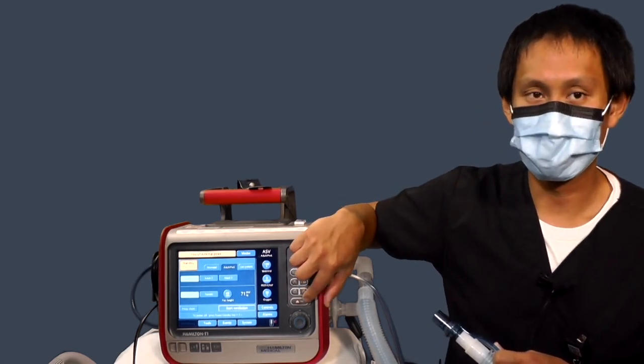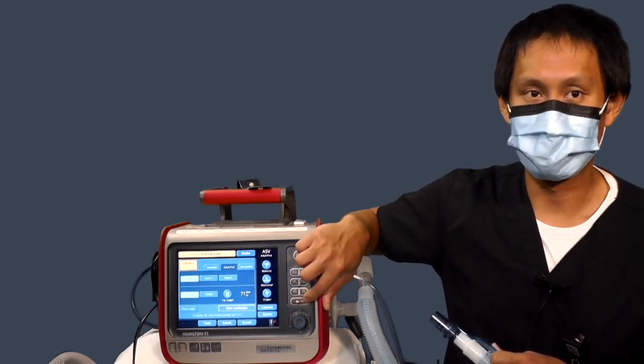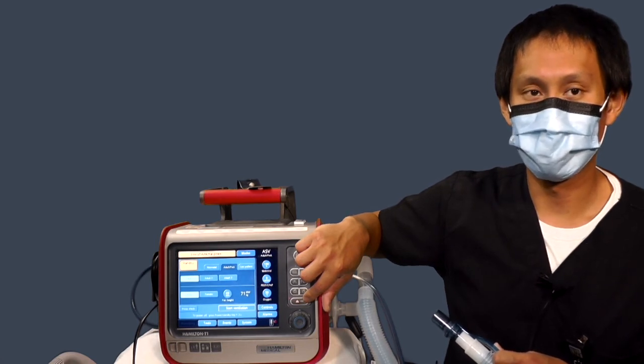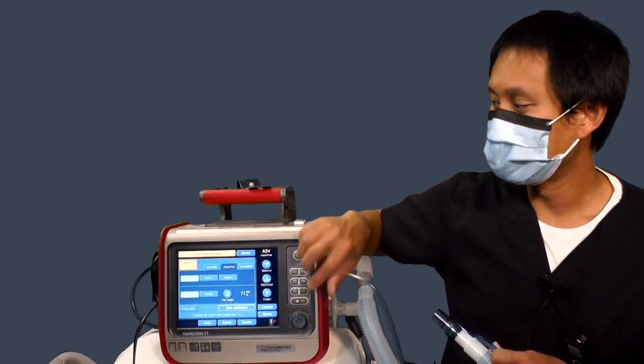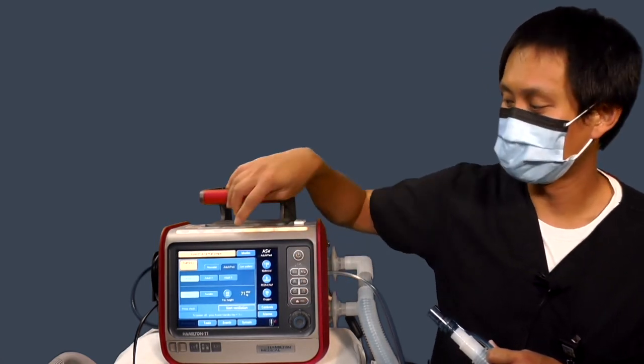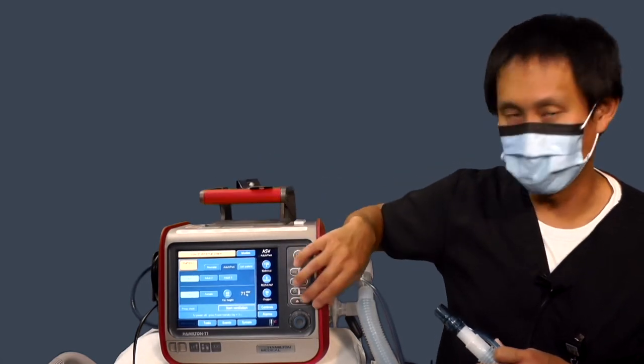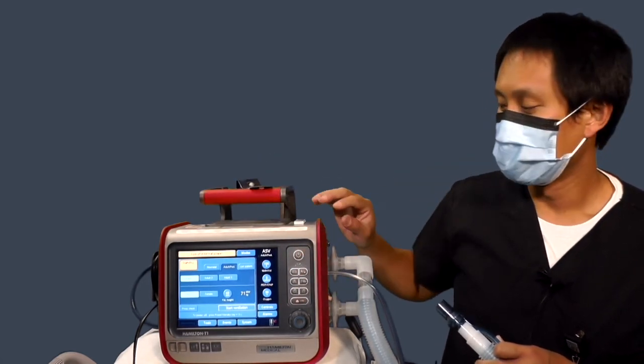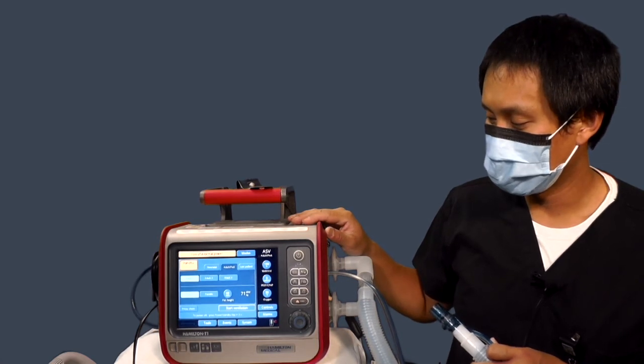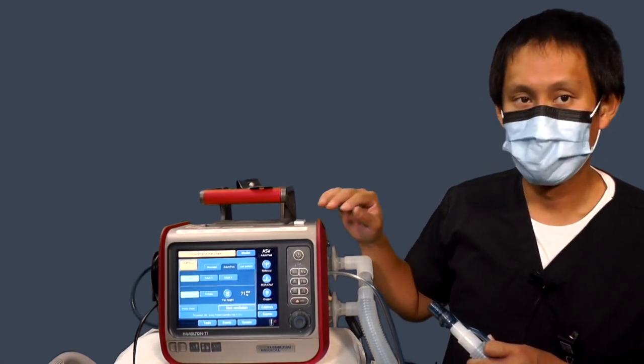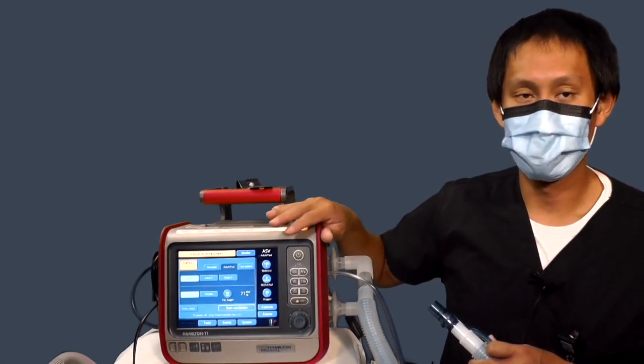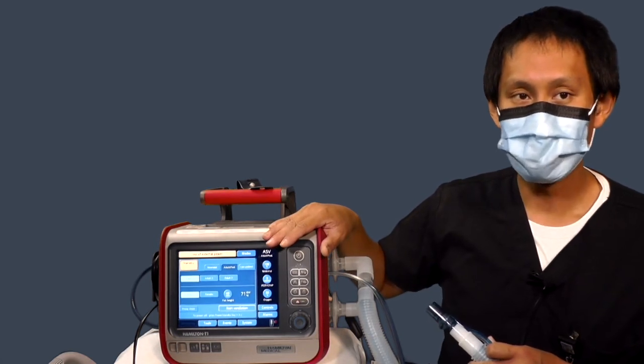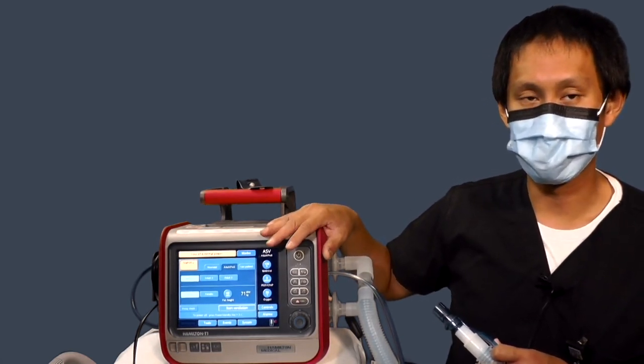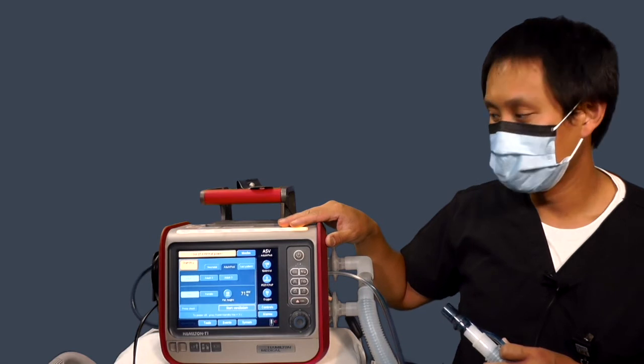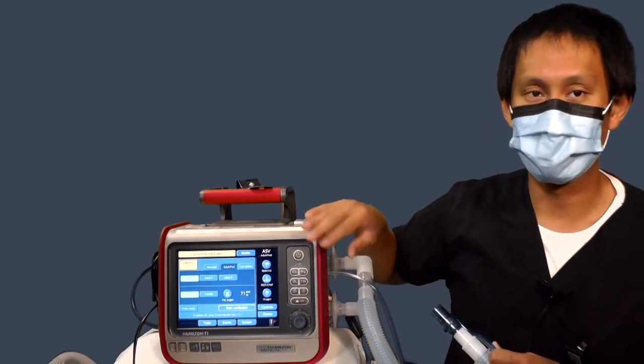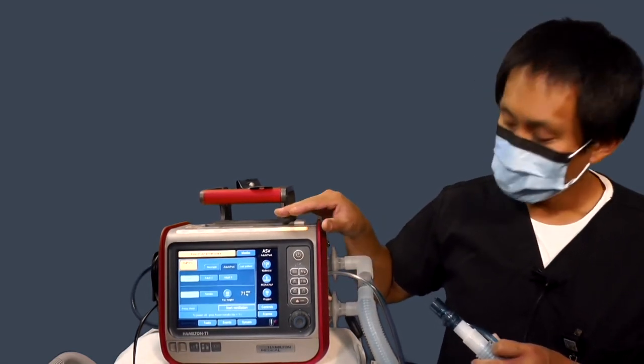Below everything will be your alarm silence button. It gives you 2 solid minutes of alarm silence. The lights will still be flashing, you'll still be getting the messages, but it'll silence the alarm for you. One advantage of this ventilator is that as it's alarming, you're not locked out of the ventilator. You can still make changes with the ventilator as it's alarming. You do not have to hit the silence first before making changes.